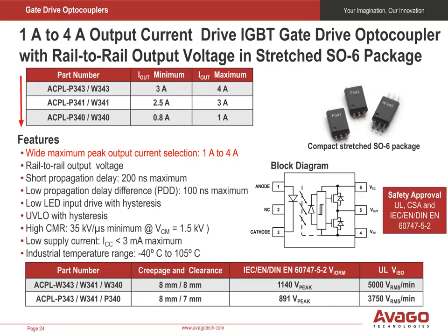Here we show our basic rail-to-rail isolated gate drivers that have driving current from 1 amp to 4 amps maximum, in the very small stretched SO-6 package. Rail-to-rail output voltage means the output voltage level is very close to the VCC supply voltage when fully turned on and very close to the VEE voltage after the IGBT is turned off. The propagation delay time TP and propagation delay difference between devices PDD are 200 nanoseconds and 100 nanoseconds respectively. These short times minimize dead time and improve efficiency. Other benefits include a high CMR of 35 kV per microsecond minimum, a common mode voltage of 1.5 kV, under-voltage lockout with hysteresis, low LED input current drive requirement with hysteresis, and an operating temperature range of minus 40 degrees C to 105 degrees C.